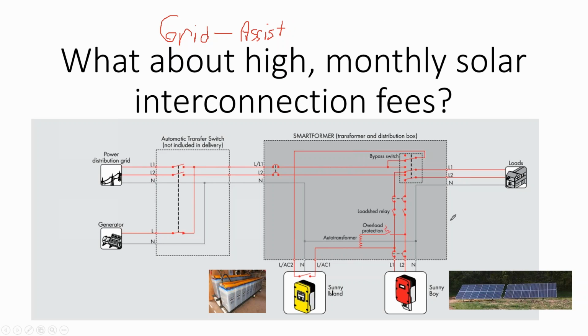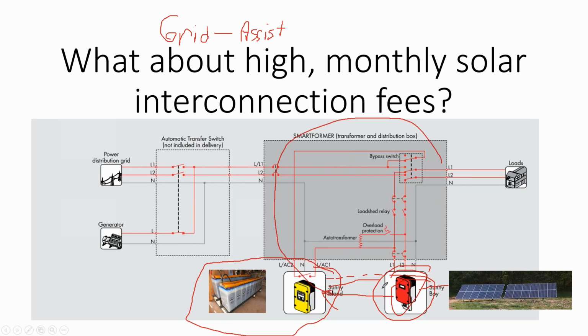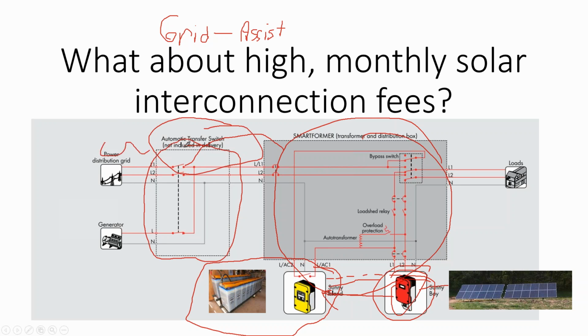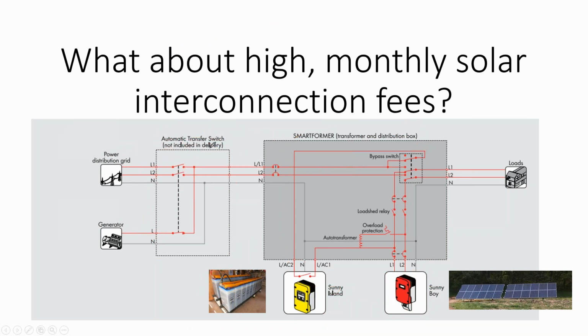Under the traditional off-grid setup, you'll have your solar array, which may or may not be AC coupled to your battery inverter. Either it lands as a charge controller on the DC side of a battery inverter, or it's a standalone inverter with a communication circuit running between the two. Then you have your electric service panel. If this is a grid connected system also set up for off-grid mode, you'll have some sort of transfer switch — whether a whole house transfer switch where power comes into the property, like with a backup generator, or a transfer switch just on a critical load panel.